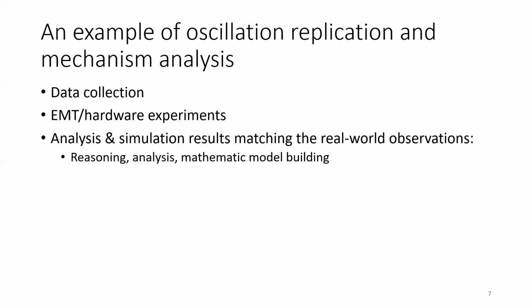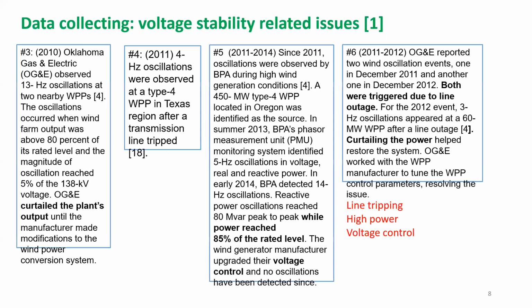In the next couple of slides, I'd like to give an example regarding weak grid voltage stability related oscillations. These four events are taken from the task force paper, reference 1, which has 19 events. Numbers 3, 4, 5 and 6 share very similar features. Oscillations occur at less than 10 Hertz, sometimes 13 Hertz, but mainly 3 or 4 Hertz. When a line trips or when wind or solar power ramps up, oscillation happens. Afterwards, you can tune the controller, called the voltage control. Especially event number 4 is the Texas event, based on the ERCOT paper. The voltage control can be tuned down to make the oscillation go away.